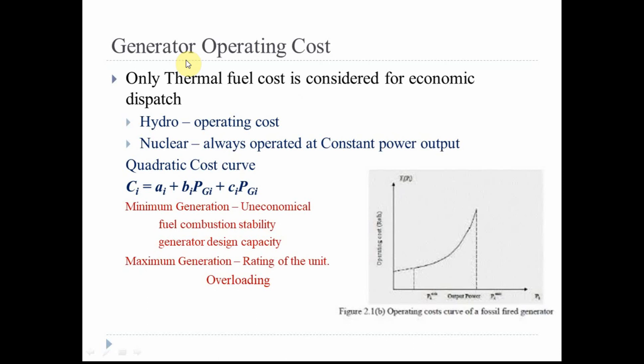Nuclear power plants are not included for economic dispatch either. We use the entire nuclear plant capacity to supply the load — for example, if a nuclear plant has 500 MW capacity, the entire 500 MW is used. Unlike a thermal power plant, we use the entire rating of the nuclear plant, so it is always operated at constant power output. Since startup and shutdown costs are very high, frequent switching is not possible, so nuclear plants always serve as base load. Hence they are not included in the economic dispatch problem.